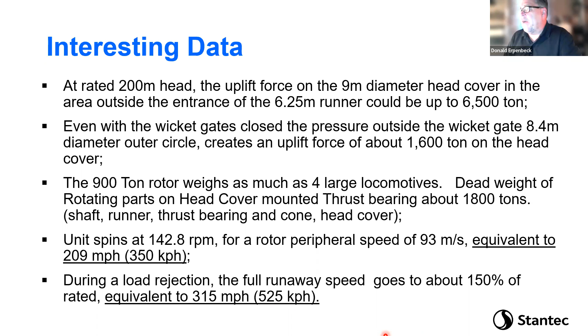Now, what happens when it goes to overspeed and we have a load rejection? This type of turbine, different turbines respond differently. The speed can increase by 50% once it's disconnected from the load, but it still has water going through it. All those other turbines were going to go upwards to about a little over 200 RPM, which would give you a speed of 525 kilometers per hour on the tip velocities on the rotor. So while the RPM is not fast, the end effect, because of how big the radius is on these things, does give you tremendous velocity and power.